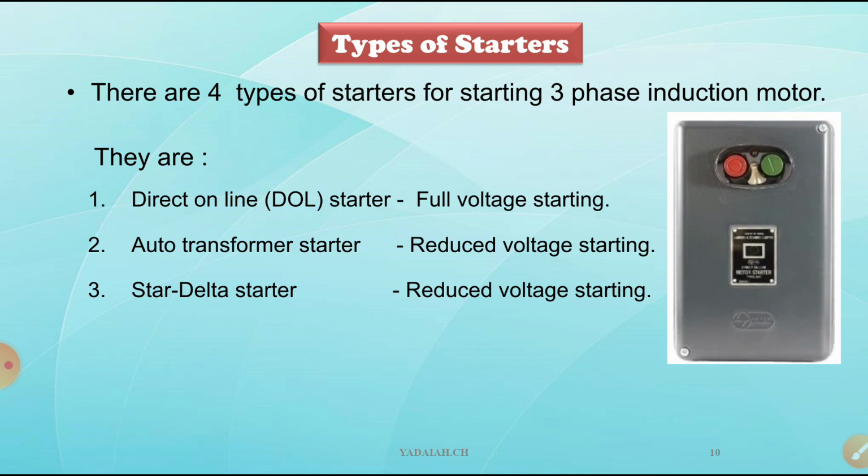Whenever you go to wheat flour mills, the operator will operate the motor for the wheat flour purpose. He can start the motor and push one starter to one side. After observing for 10 seconds, he will pull the other side knob. That means initially it is in star connection, and after the motor picks up speed, it goes to the delta connection. So it is also very famous.